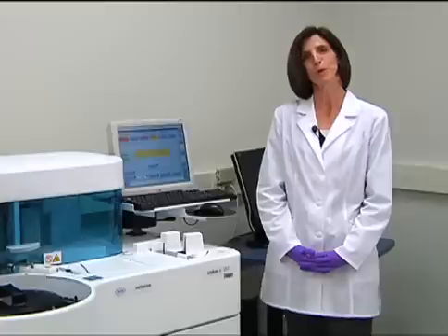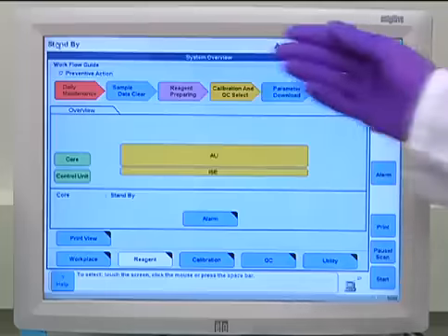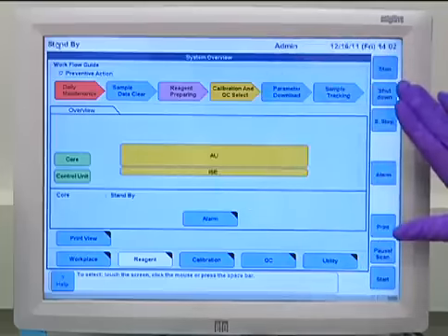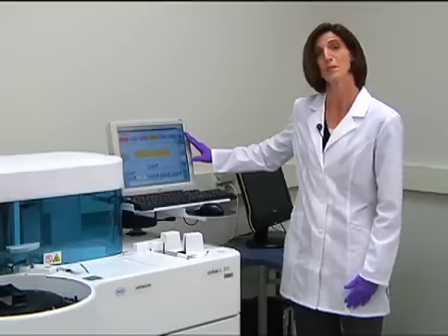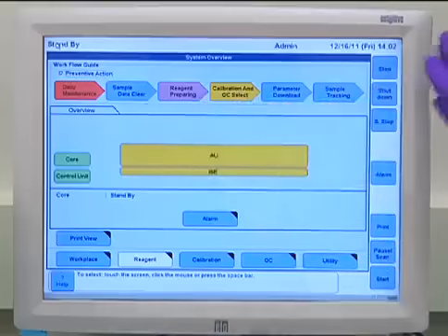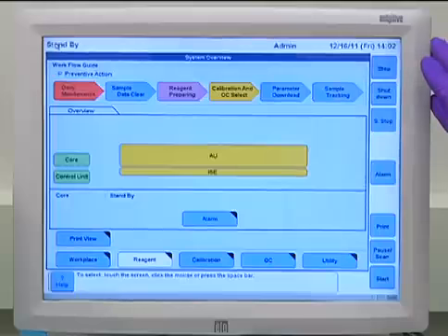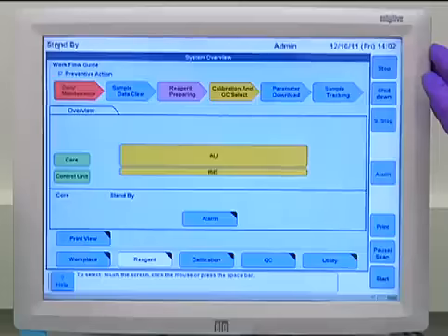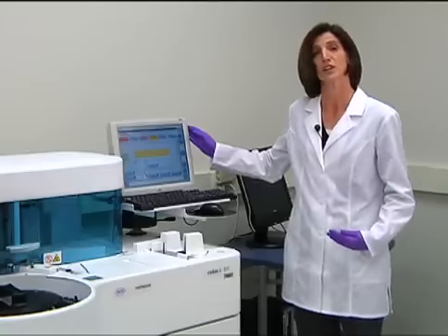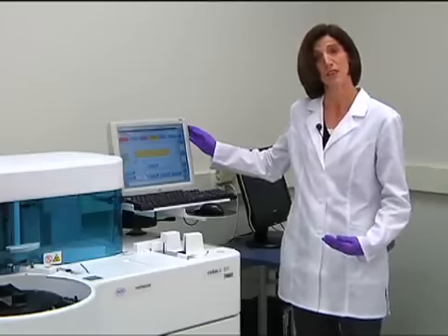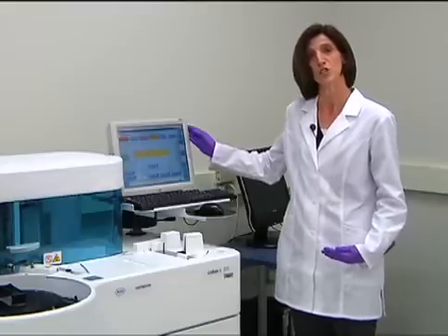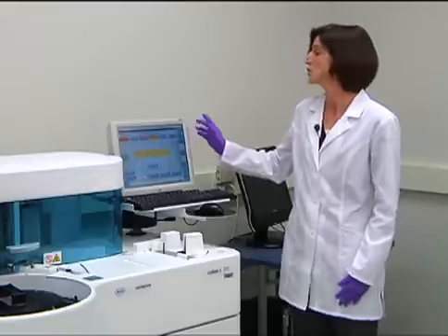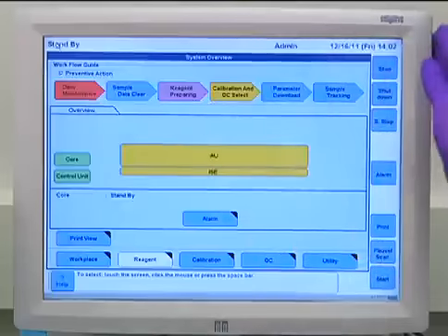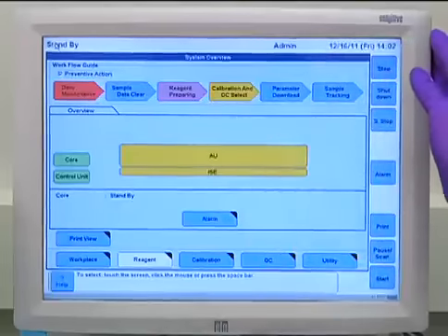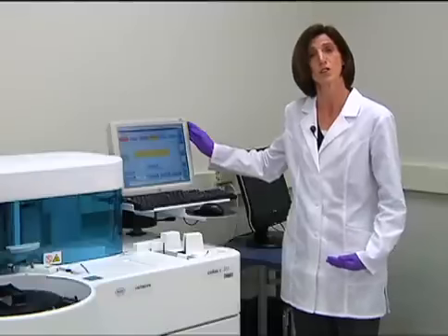So we'll start our daily preparation by first looking at the system overview screen. And this is a great screen because it gives us an overall view of the system, and it uses color to grab our attention to see if there's anything that we need to attend to. We have already selected preventive action, and what that does is look ahead to let us know if we need to load any reagent to cover the day's work, and also if any calibrations are going to be due during the day. So you can see my reagent preparing button right now is purple, and that's letting me know I don't have enough reagent to get through the day.